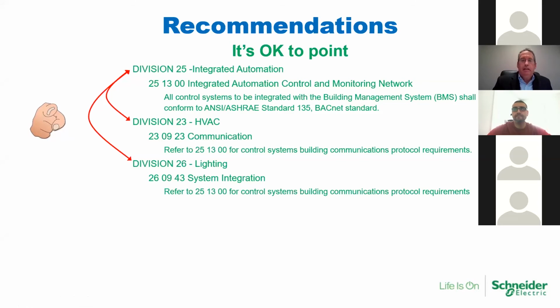In your actual spec, let's say you want to use BACnet. You put it in Division 25 as a spec item, describe it there, and now you can point from Division 23 in your HVAC system. We're going to use a protocol, we're going to use BACnet, so you refer back to Division 25.